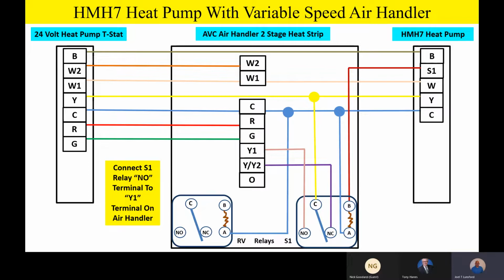Now, this is really, really important. If you've got a variable speed air handler hooked up to a heat pump, you've got to tell it it's on a heat pump. Number one, there's a jumper selection that says heat pump or AC. You put it on heat pump. As soon as you put it on heat pump, the variable speed air handler is looking for an O signal on the O terminal.